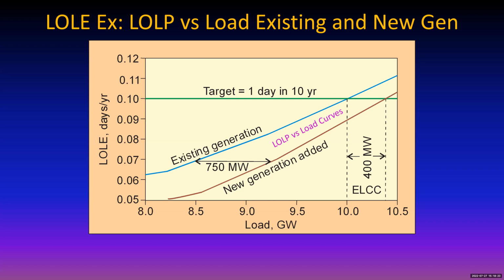Here's existing generation on the blue line. Notice that as the load goes up, the chance of that generation having a problem increases until we get to, say, 10 gigawatts of load. At that point, when this generation is supplying 10 gigawatts, the loss of load expectation reaches this 0.1 magic number.